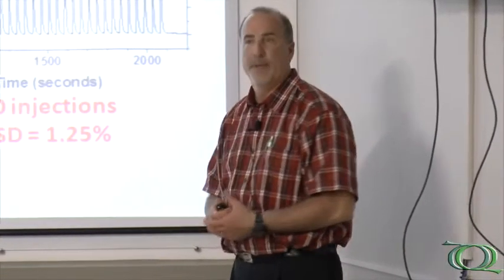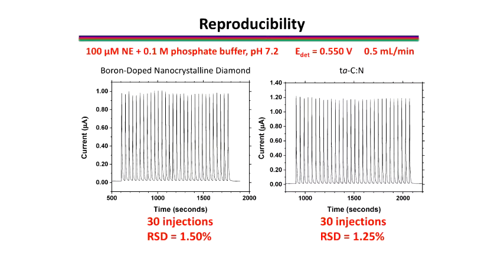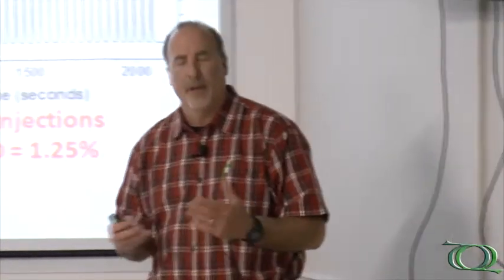If you want to do a measurement, the first detection figure of merit that you look at is how reproducible the measurement is. These are a series of injections of norepinephrine at 100 micromolar. The carrier solution is a phosphate buffer at pH 7, and we're detecting at 550 millivolts, which is out here on the plateau of the mass transport limited region of the curves. The reproducibility for both of them is very, very good — over 30 injections, a variability of about 1.5%, about 1.2% here. High reproducibility is very characteristic of both diamond and ta-C.